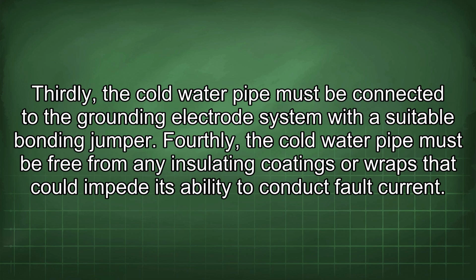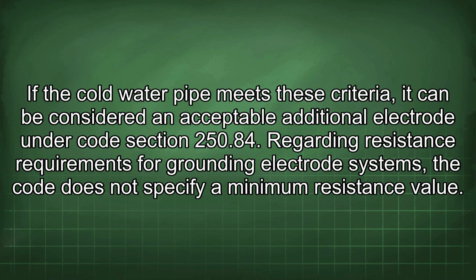Fourthly, the cold water pipe must be free from any insulating coatings or wraps that could impede its ability to conduct fault current. If the cold water pipe meets these criteria, it can be considered an acceptable additional electrode under Code Section 250.84. Regarding resistance requirements for grounding electrode systems, the code does not specify a minimum resistance value.